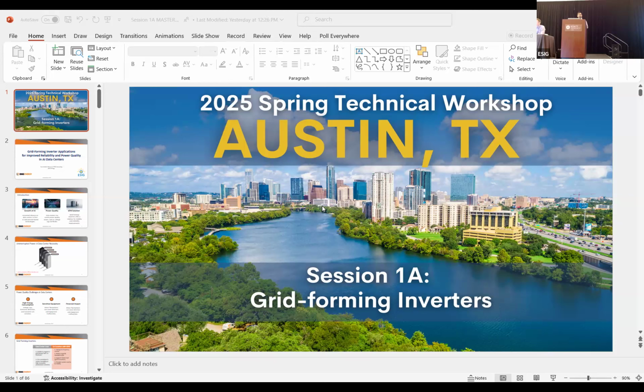So we did another evaluation with some of our members where this is a larger portion of the Eastern Interconnect, and there is this pocket in this larger portion of the Eastern Interconnect. And there are a bunch of wind plants, and there is a stability constraint in place. There is a scenario where if a fault occurs with prior outages, you're going to have, again, instability effect come up. And there are batteries in the interconnection queue in this broader region. So the idea was to try to identify, okay, can these batteries that are in the interconnection queue, if they are enabled with advanced grid support, really help this region or not? Because if they can't, then that battery is not going to be helpful, and some other solution needs to be found for this particular region of the network.